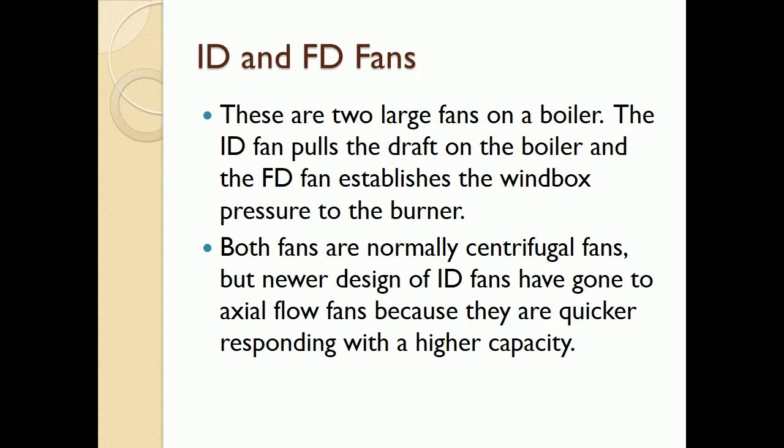The ID fan pulls the draft on the boiler, and the FD fan establishes the windbox pressure to the burner. Both fans are normally centrifugal fans, but newer designs of ID fans have gone to axial flow fans, because they are quicker responding with a higher capacity.